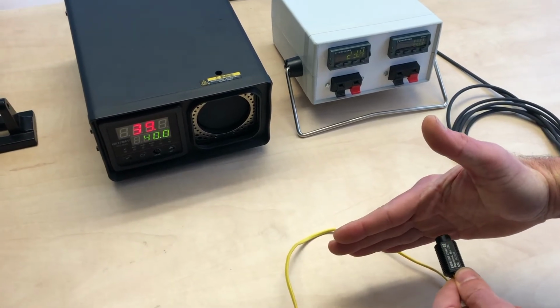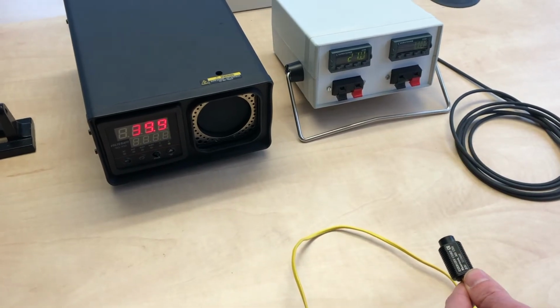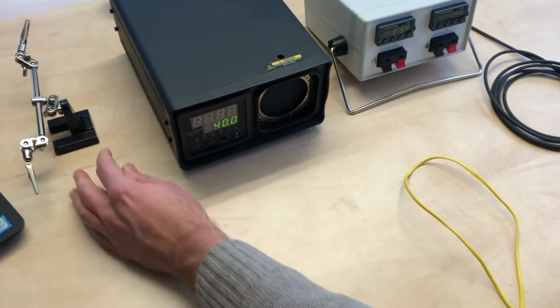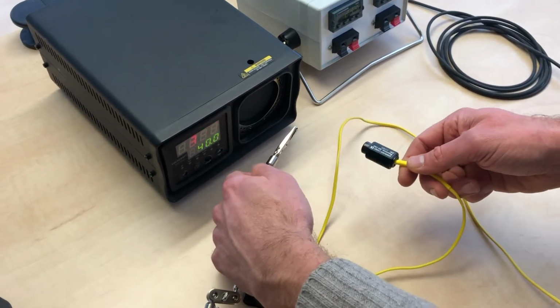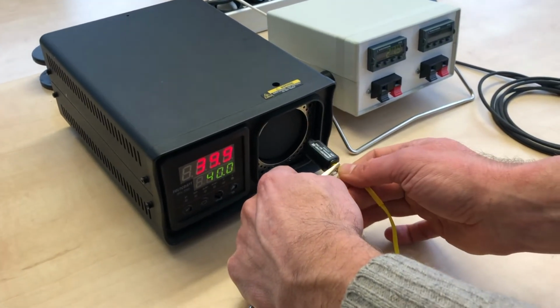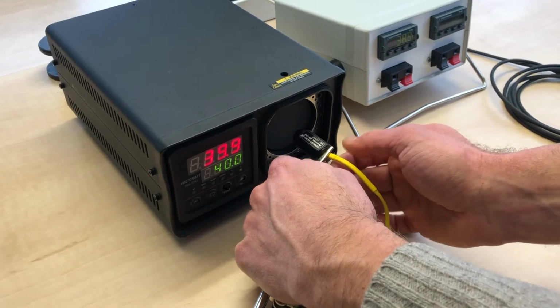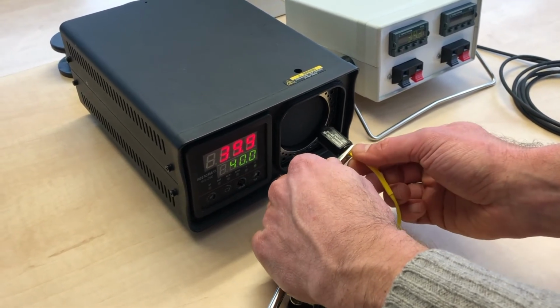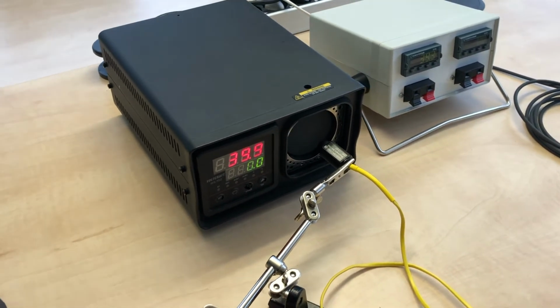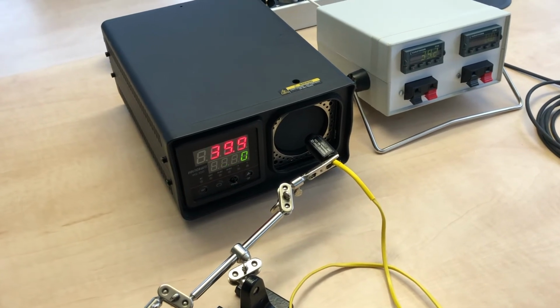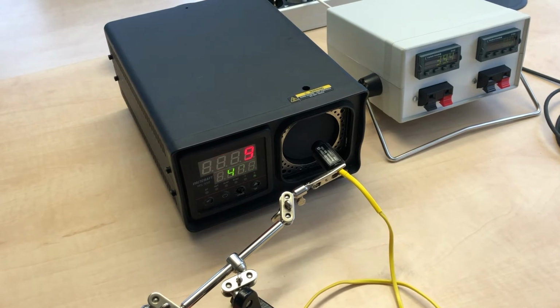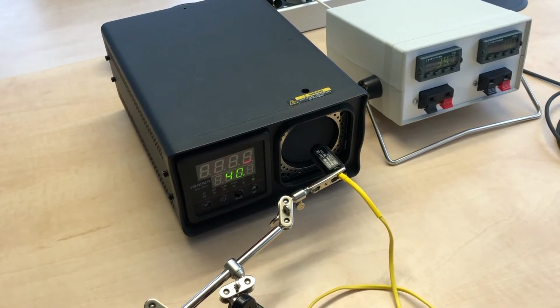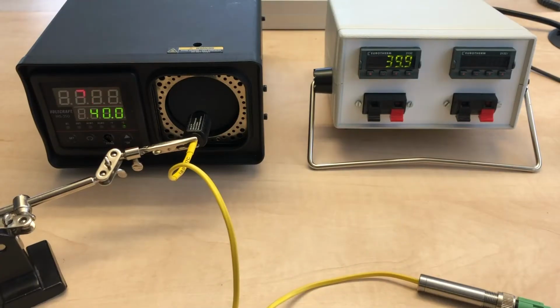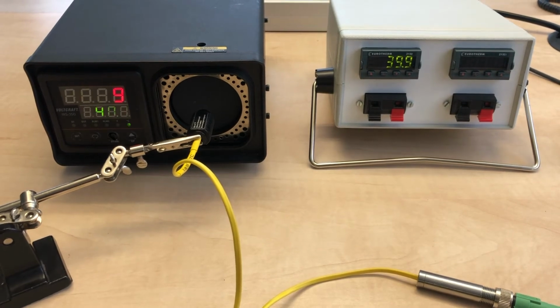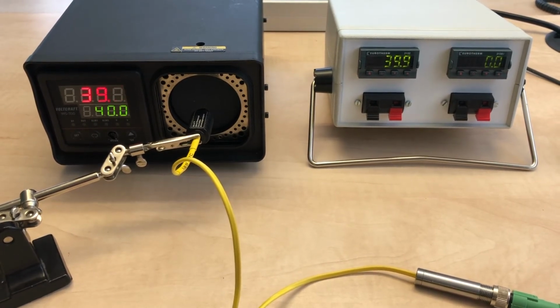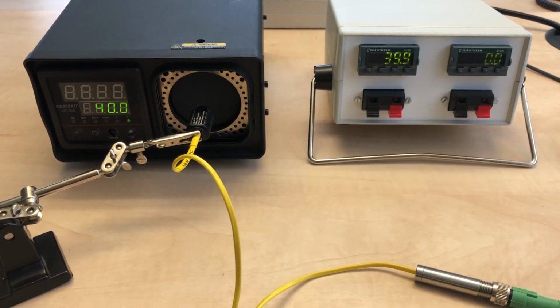What you see is already, if I put a warmer target in front of the sensor, you see a result in the screen. Also here is a blackbody calibrator. So I would like to demonstrate how this works. I put the sensor in front of the blackbody, make sure it's mounted properly, looking in the right direction. And you see that it gives a very nice temperature of the blackbody. So if you order an AutoSmart sensor with a standard calibration, so minus 30 to 70 degrees C, or 0 to 100 C, or 0 to 250 C, this is how it works.